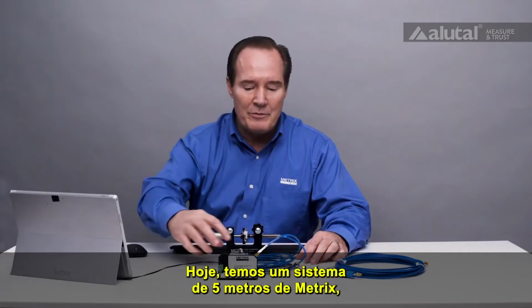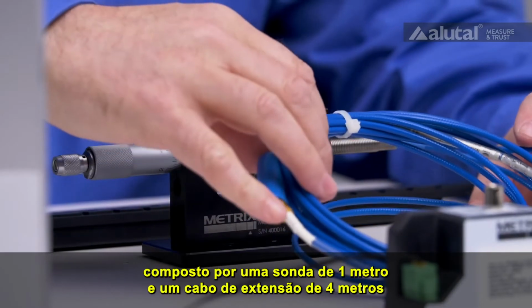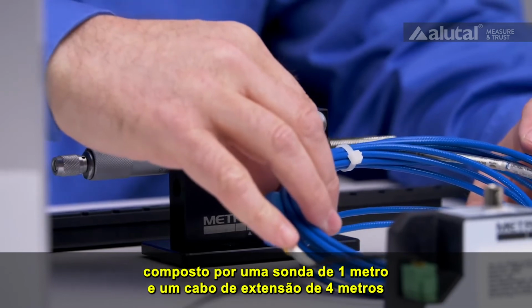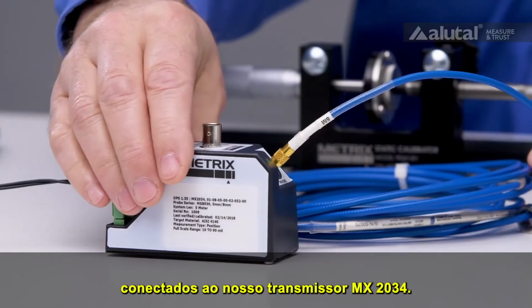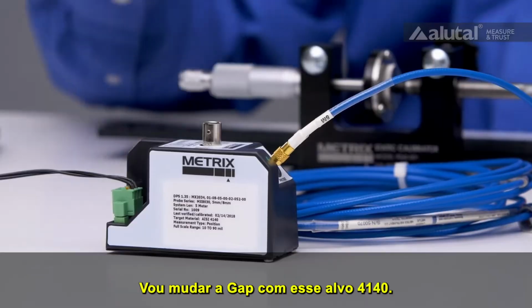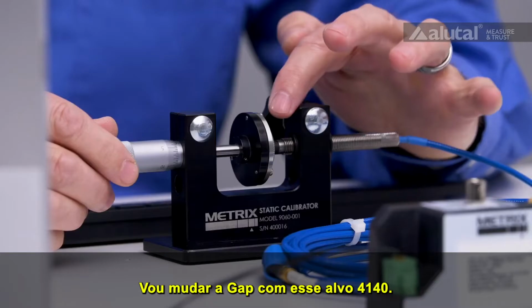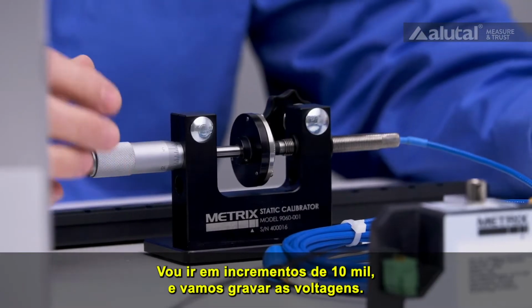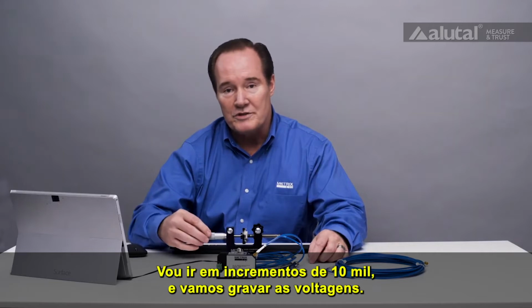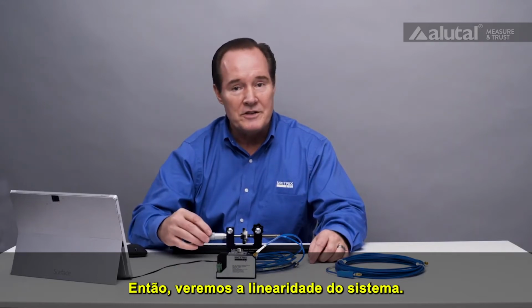Today we have a 5-meter Metrix system. We have a 1-meter probe and a 4-meter extension cable going to our MX2034 transmitter. I'm going to change the gap with this 4140 target. I'm going to go in 10 mil increments, and we're going to record voltages. And we're going to see the linearity of the system.